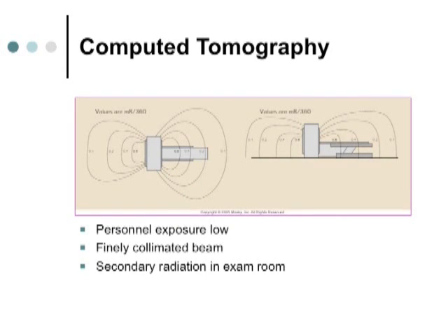If you're standing near a CT scanner, the isoexposure curves coming out are usually very low because CT uses a slit beam — the beam comes out in a very narrow slit, not in all directions like a conventional x-ray. So the exposures coming out of the gantry are very, very low, which is why you sometimes see parents standing in the room during a pediatric scan.